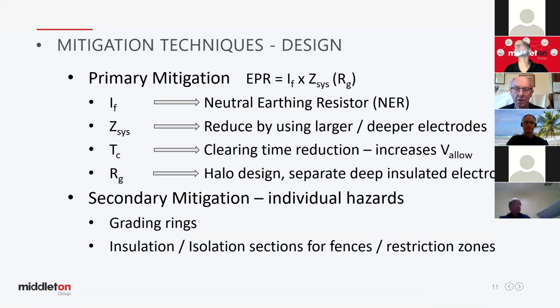Question relating to the halo design, Scott. With that deep rod, are you talking about the top half insulated and the bottom half bare then? Correct, yeah. The top of the electrode, indeed the whole substation, needs to be insulated from the surface. So there are special culverts for a pad mount that you can purchase. They're insulated, and there are some specialised devices to manage how your HV conductors come in and out of that sub. You've got to look at safety and design nowadays. This has got to last for the lifetime of the asset, so you don't want movement, vibration, etc., to corrupt the insulation at that pad mount.